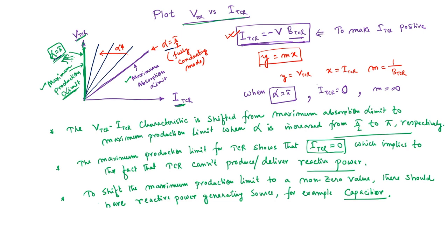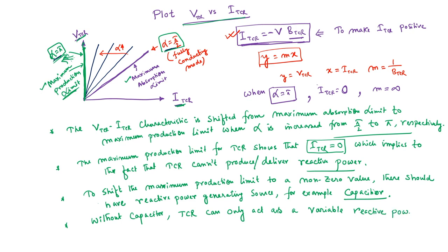So, from this we can understand that this TCR can be operated from alpha equal to pi by 2 to alpha equal to pi, and by operating so, we can only control the var absorption.